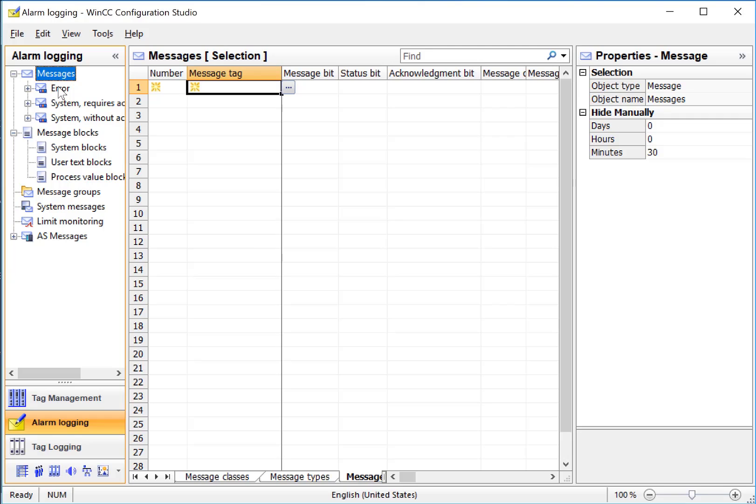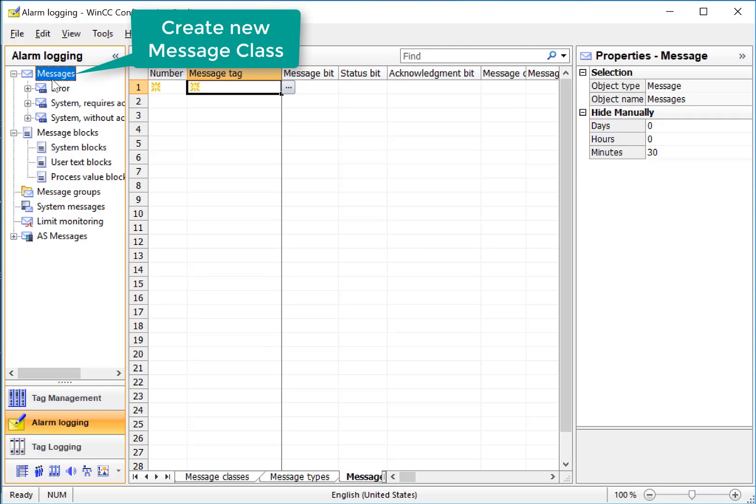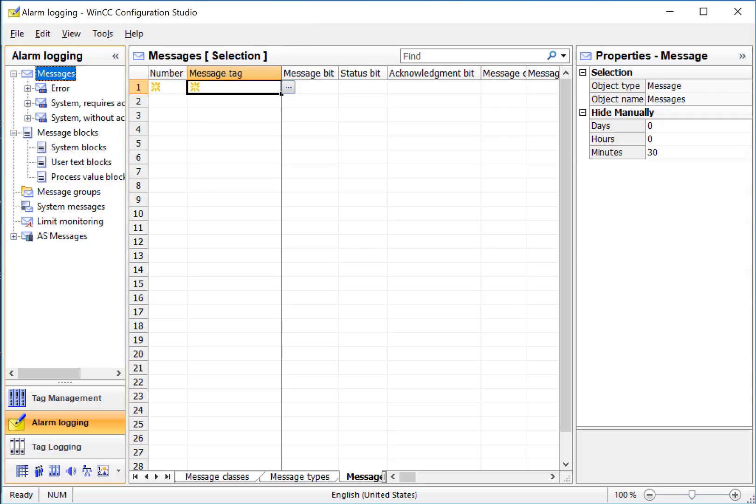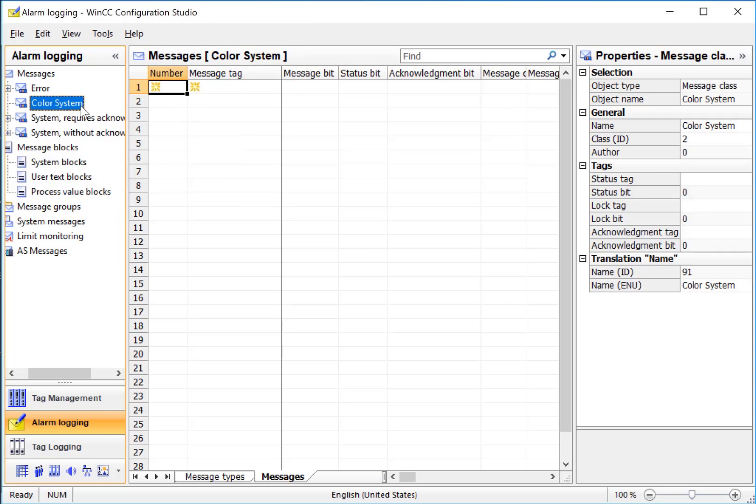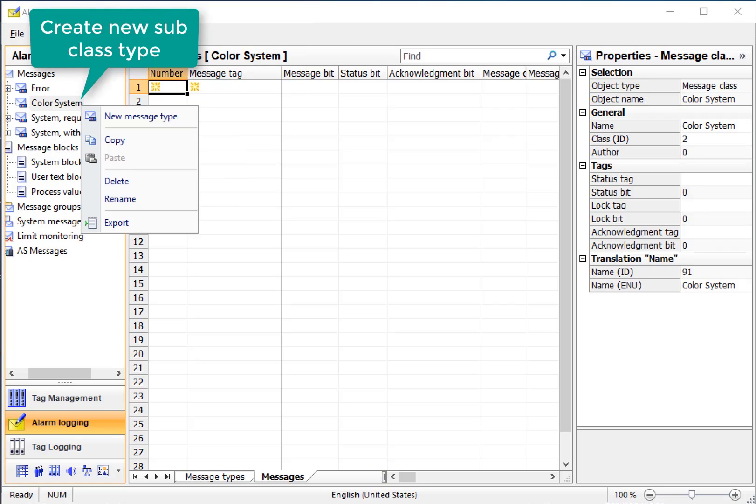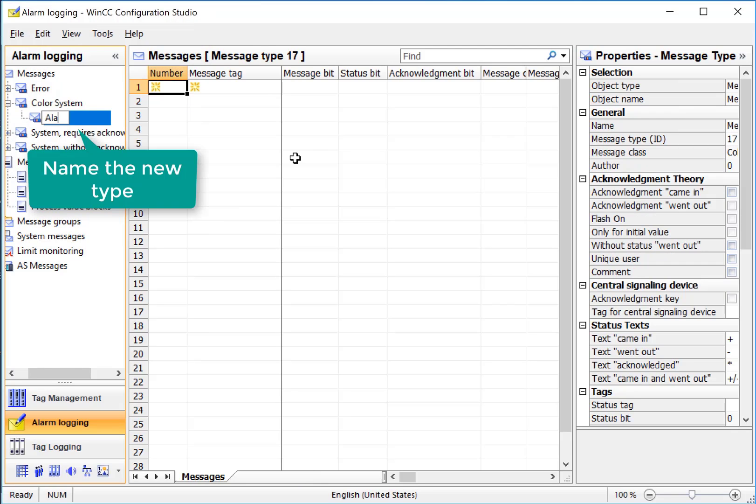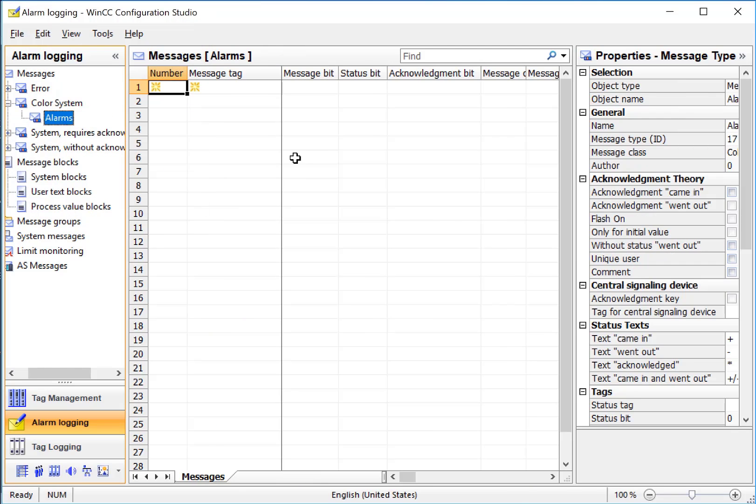Under Messages, these are alarm class and subclasses, and you can use these to organize your alarms. So we'll create our own class for our color system. Right-click, New Message Class, and we will call it Color System. Under Color System, we'll right-click and add a new message type, and we'll just call this Alarms.